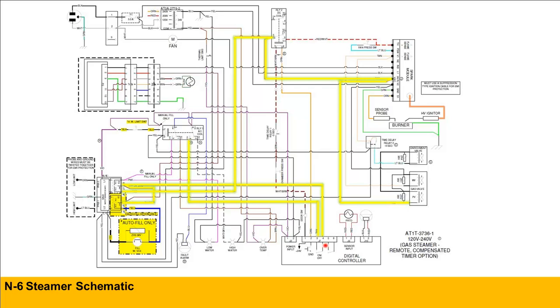So for, let's say, okay, we checked, we do have 24 volts AC coming from the control board, so we have to keep going down the line. So since we do have 24 volts AC coming from the pin of J74, now we've got to check the same, make sure that's the input. Now we've got to test to see if we have an AC output from the water board.